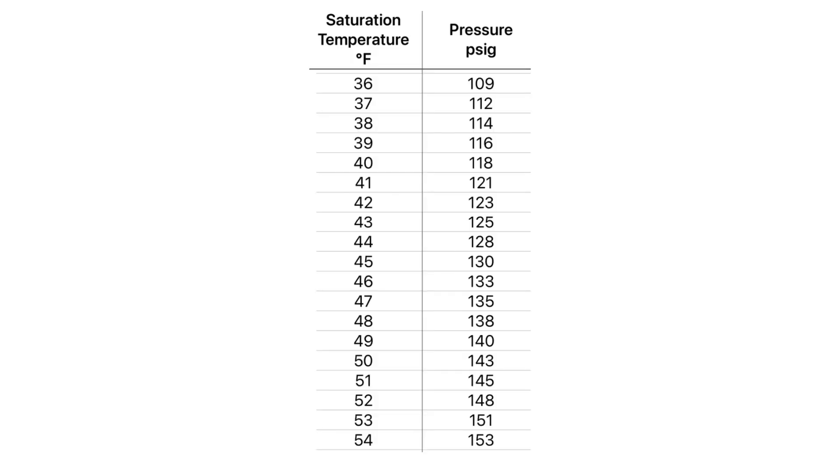From here, you could use a pressure-temperature chart to make your calculation based on your suction pressure. For example, if your suction pressure was at 130 psi, you would have a saturation temperature of 45 degrees. Note, if you had your low side gauge hooked up to the unit, you can use your gauge as a T-P chart.